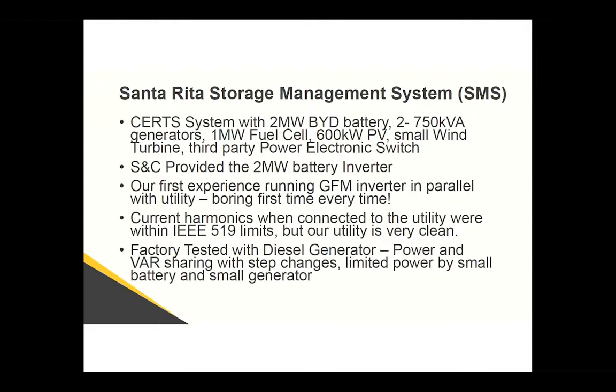So in this case, we started running in parallel with the utility in the grid forming mode. And my concern was, okay, as soon as we do that, we've got the fault current of the utility that, as an example, in our shop was on the order of 40,000 amps and could do some nasty things if you got the angles wrong. And so we've been concerned about that all along. So when we started running this system, we synchronized up, turned it on, and it was really boring, which was great. It just worked. And it stayed at the power level that we had commanded. When we commanded a new power, we go to that new power. It worked the first time right away.